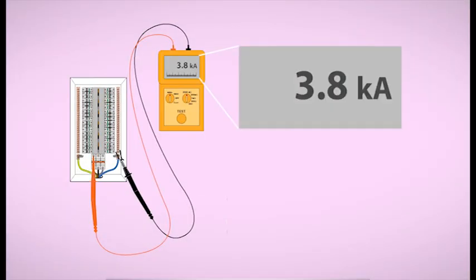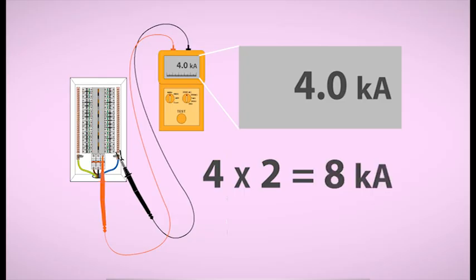Don't forget as well that the prospective fault current is the highest value obtained from either the prospective short circuit current test or the prospective earth fault current test, and this is for each supply if there's more than one. It's important to mention that some instruments will not be suitable to measure prospective fault currents on three-phase supplies, so check your instrument can before you do. If your instrument doesn't, it doesn't matter, because it's perfectly acceptable to measure prospective short circuit current between each phase and neutral and multiply your highest reading by 2 to give an approximate value of prospective short circuit current for the three phases.